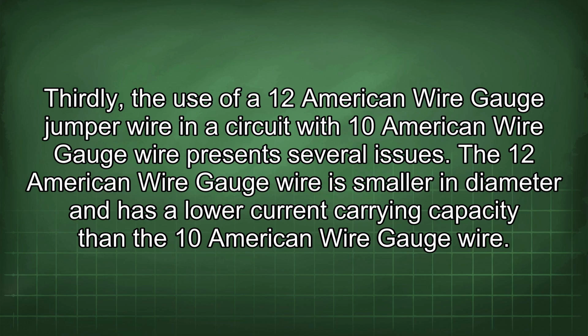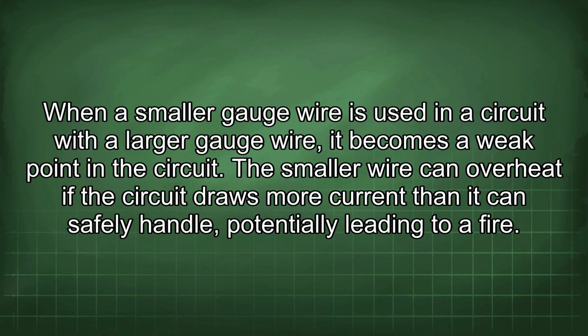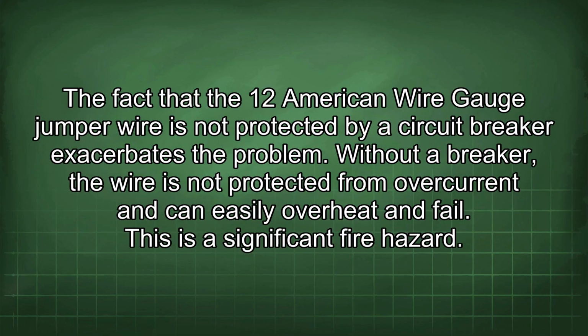Thirdly, the use of a 12 American wire gauge jumper wire in a circuit with 10 American wire gauge wire presents several issues. The 12 American wire gauge wire is smaller in diameter and has a lower current carrying capacity than the 10 American wire gauge wire. When a smaller gauge wire is used in a circuit with a larger gauge wire, it becomes a weak point in the circuit. The smaller wire can overheat if the circuit draws more current than it can safely handle, potentially leading to a fire. The fact that the 12 American wire gauge jumper wire is not protected by a circuit breaker exacerbates the problem. Without a breaker, the wire is not protected from overcurrent and can easily overheat and fail. This is a significant fire hazard.